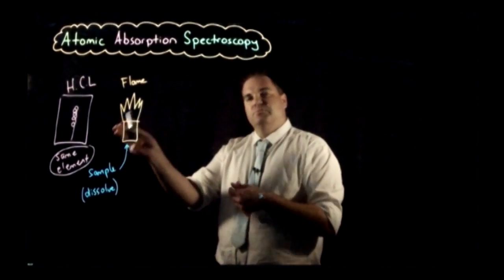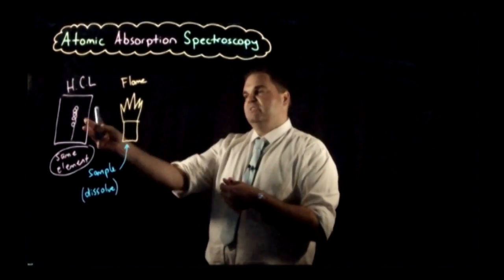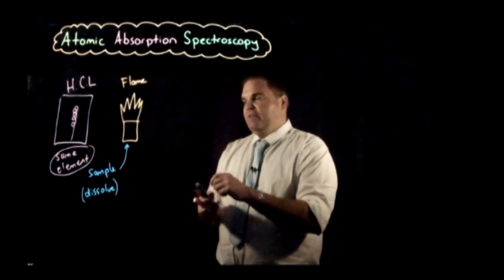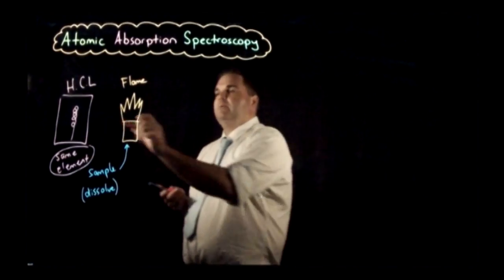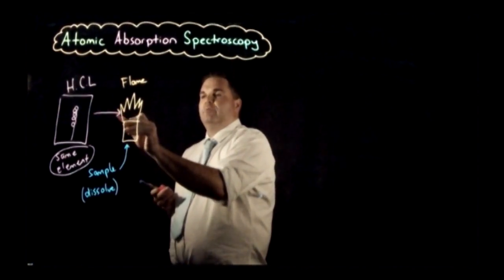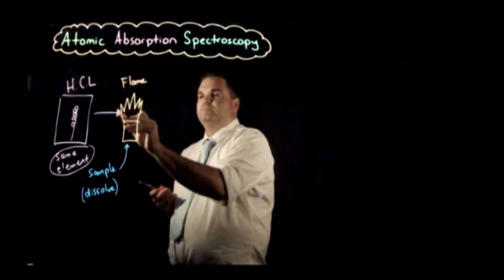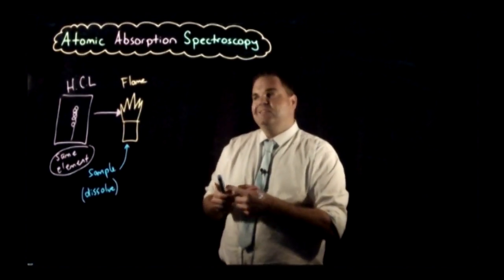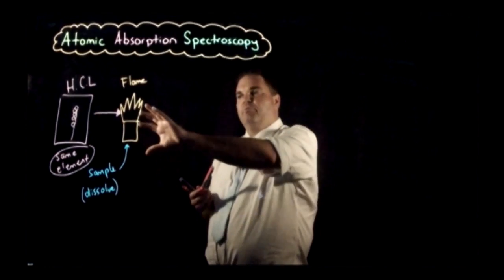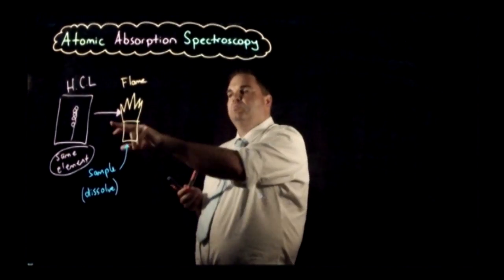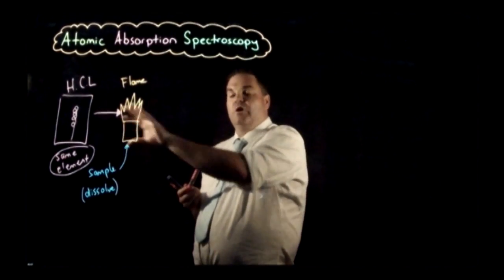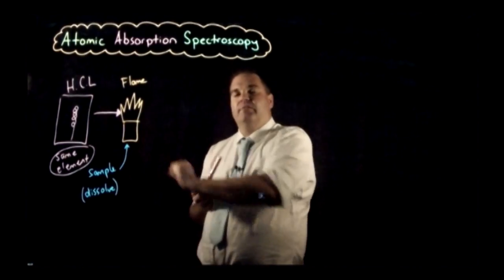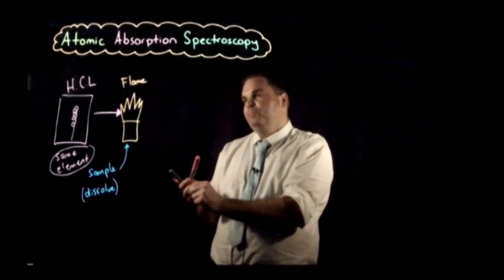The cathode lamp is absorbing energy and emitting photons in the form of light. These photons come out of the hollow cathode lamp and pass through the vaporized sample. If we have the atoms we're trying to determine inside the vaporized sample, some of that light will get absorbed — only those specific atoms, because of the unique wavelength coming out from that hollow cathode lamp.